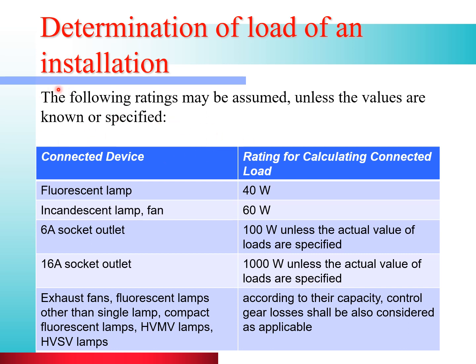As per NEC 2011, for the determination of the load of an installation, the following ratings may be assumed unless the values are known or specified. In this table, the connected devices and their calculated connected load ratings are given. The first device is the fluorescent lamp, for which the rating assumed for calculating the connected load is 40 W.